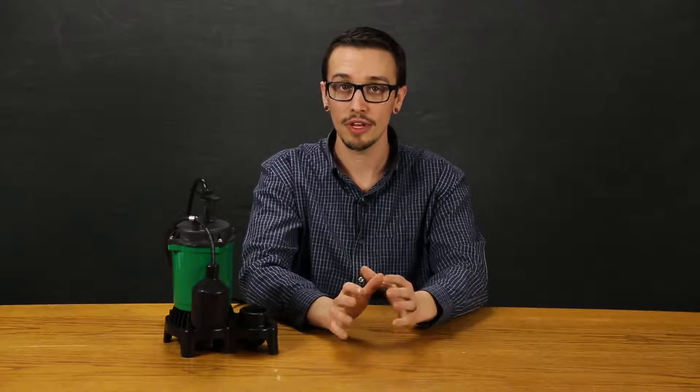This pump features total maintenance free operation. The motor though small features a permanent split capacitor which is designed for maximum efficiency and gives maximum available starting torque compared to the shaded pole motors commonly found in this particular size of sump pump.